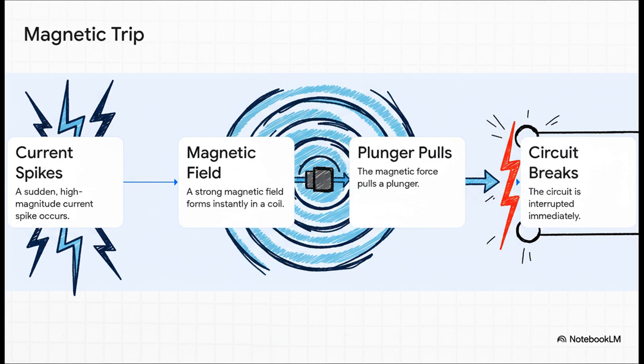But for a crazy, violent short circuit, you don't have time for something to slowly heat up. You need instant action. And that's where the magnetic trip comes in. A huge surge of current creates this powerful magnetic field inside a coil, which instantly yanks a small plunger. This isn't a slow bend, it's a snap. It's like a mousetrap. It triggers the mechanism immediately, cutting the power before catastrophic damage can happen.